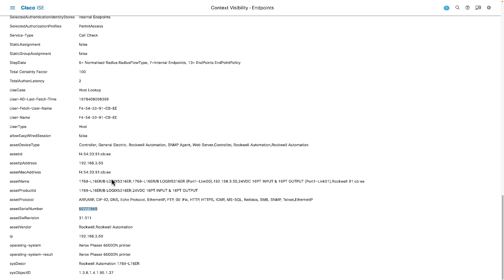Inside ISE, I have the ability to create a profiling policy using any of these values — for example, a profile specifically for Rockwell devices identified as an L16ER, or devices running a specific firmware. However, when bringing security to the industrial space, the type of device alone isn't enough information. A Programmable Logic Controller — the P being programmable — means that the exact same hardware and firmware could be doing very different tasks depending on how it's been programmed. That's where leveraging the group information as a custom attribute really comes into play.